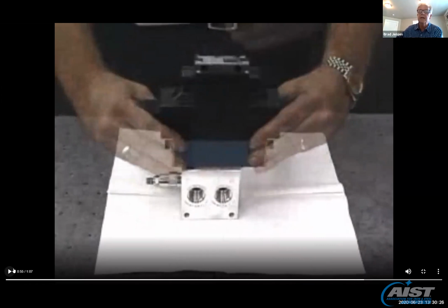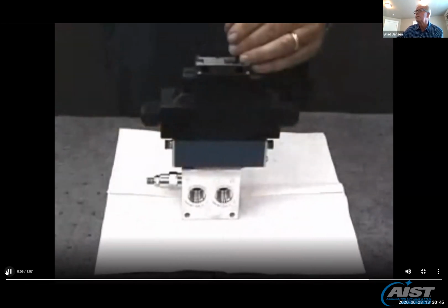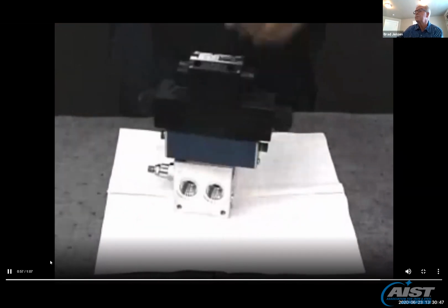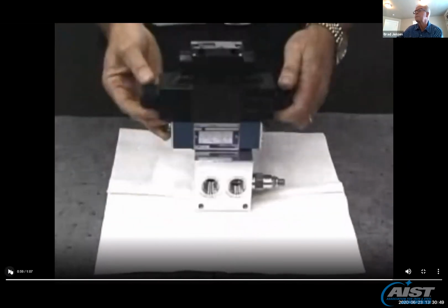Now you notice he replaced the seal plate. That means that valve, as you saw here, could be rotated either way. If it was rotated the wrong way, the functionality of that kicker cylinder is going to be completely backwards with the controls. So let me end this.